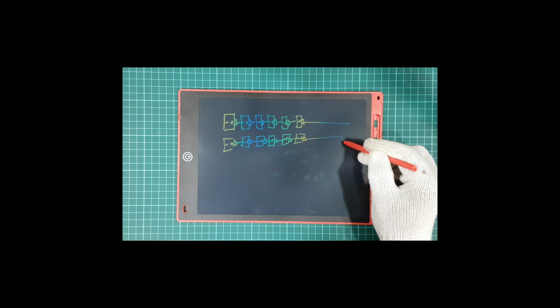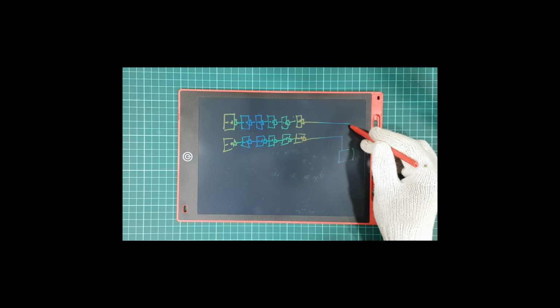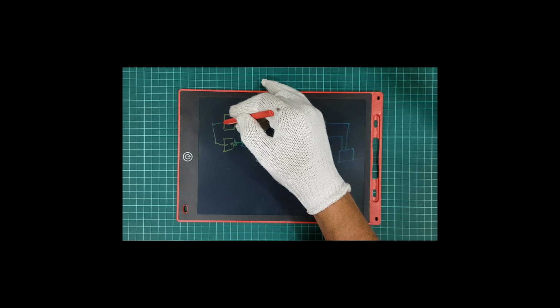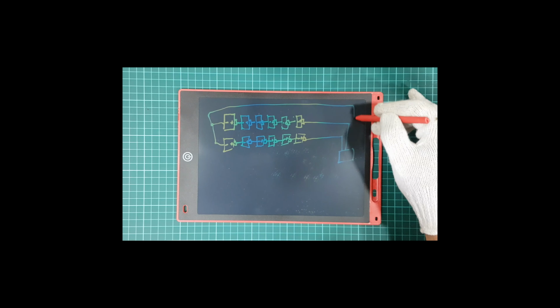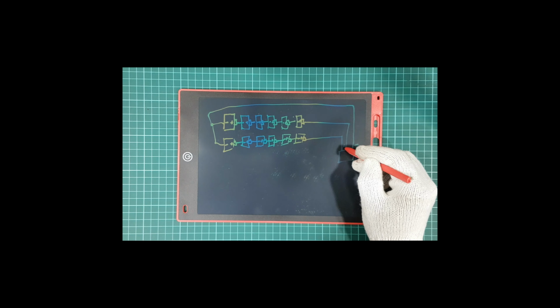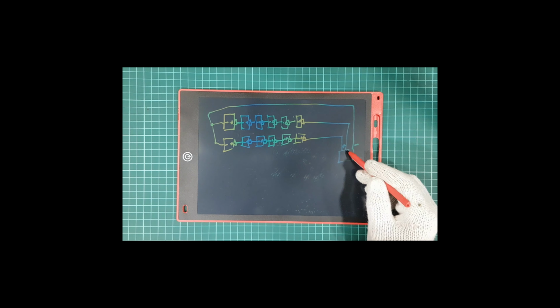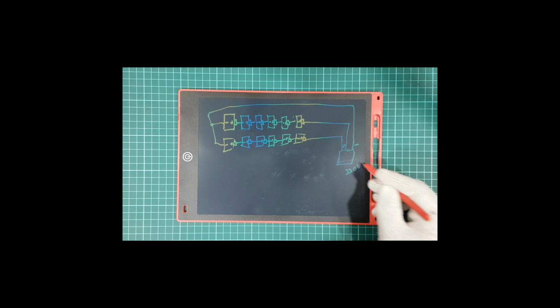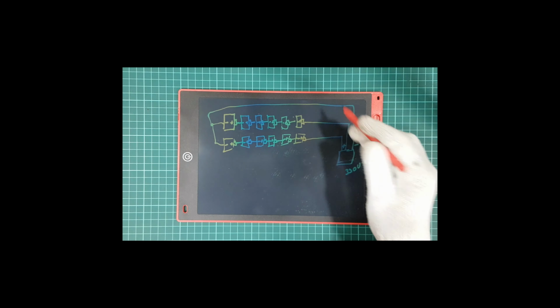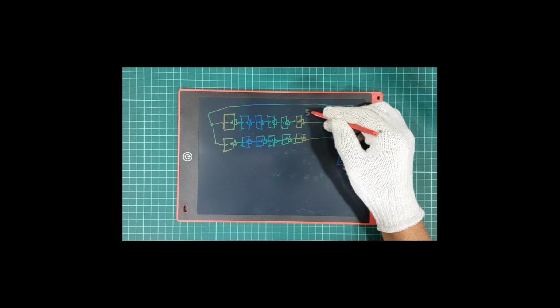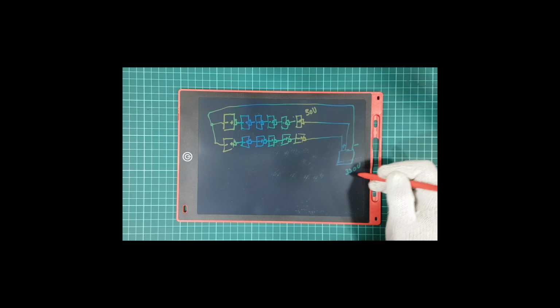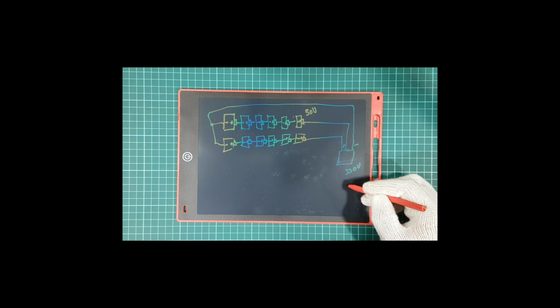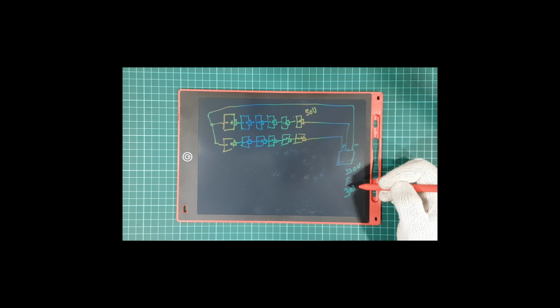These will then go to our solar system, the MPPT, and then these get connected together, and that goes also to the MPPT. So we'll have a minus here and a plus that side. My solar unit is rated at 350 volts maximum, if I remember correctly. So having 6 panels, that is 50 volts at no load, will mean I will only be delivering 300 volts into the system, which is well within its capacity, and I won't risk damaging it.